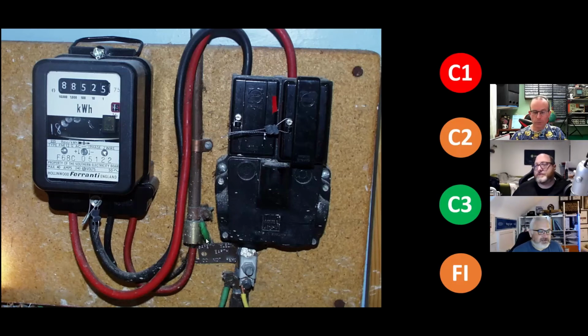Right. So what's everyone coding this then? We've got C2s, I do, building up pyro on this one. Is this in an enclosed area, cupboard, or what? No, this was literally by the front door on the ground level. So you open the front door, and this was basically under the stairs, just behind it. So no cupboard, completely accessible to anybody. If you put your stuff in there, you could bash into it and break bits. I'm thinking C3 here, but with the pyro and the fragility of it, and children and all the rest of it, I'd probably C2 it just based on that pyro. I'm on the same ballpark.